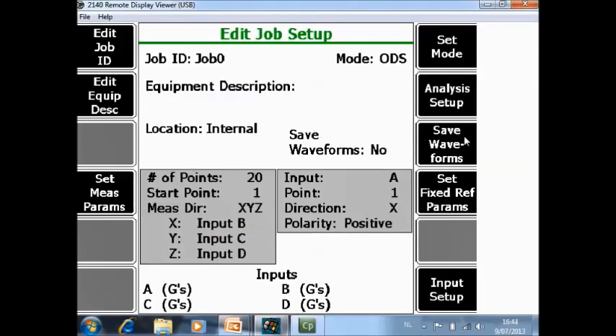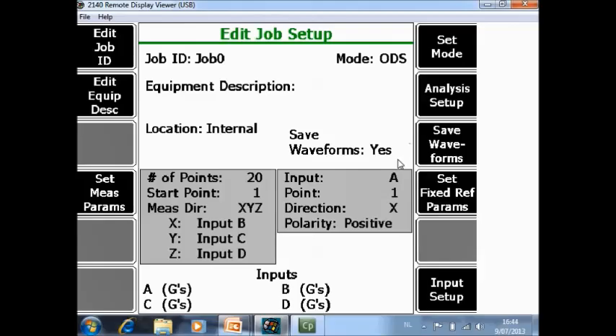Then you can specify if you want to save the waveforms yes or no. I always recommend you to store the waveforms as well. This function is coming due to some legacy issues from the time that waveforms were taking a lot of memory of the analyzers and to save some memory this was an option. But now memory is no longer an issue, so I strongly recommend to always store the waveforms.